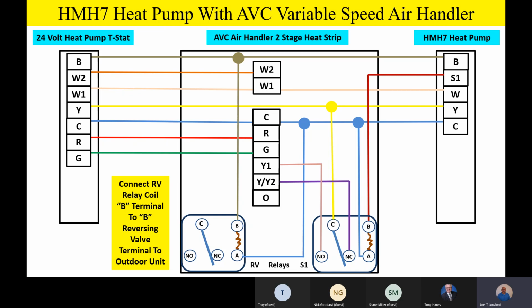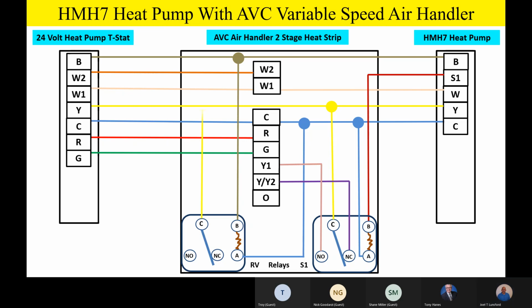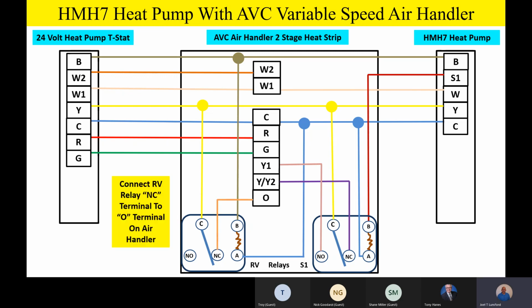So the relay is just sitting here in the cooling mode doing nothing, but when we go in the heating mode of operation, we energize the B terminal on the thermostat. We're going to energize, and we're going to click that relay, that RV relay. Now watch this. The common terminal for the switching contacts goes up to Y on the RV relay as well. So anytime you have compressor operation, you're going to energize that common terminal for the switching contacts. Now the normally closed contact on the RV relay goes up to the O terminal.